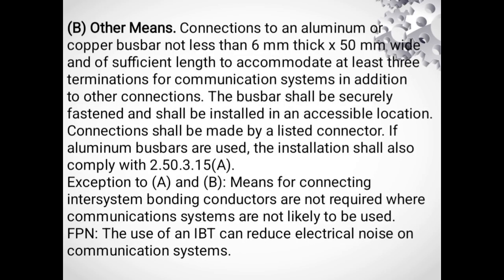B. Other means. Connection to an aluminum or copper bus bar not less than 6 mm thick by 50 mm wide and of sufficient length to accommodate at least 3 terminations per communication system in addition to other connections. The bus bar shall be securely fastened and shall be installed in an accessible location. Connection shall be made by a listed connector if aluminum bus bar are used. The installation shall also comply with 2.50.3.15a. Exception to A and B: means for connecting inter-system bonding conductors are not required where communication systems are not likely to be used. FPN.